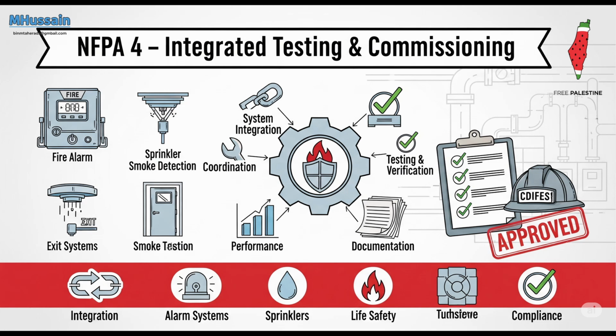Leave no stone unturned. What about retesting? What if something fails during the test or they have to make a change? Good question. The standard says testing must be repeated if any changes or corrections are made to systems during the testing process that could affect their overall functionality. You fix something, you test again. The whole test? Not necessarily the entire thing from scratch.